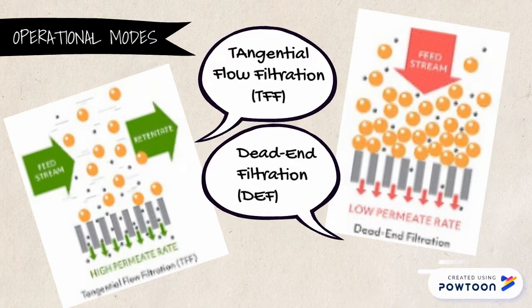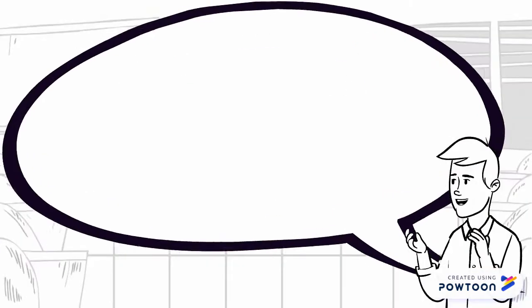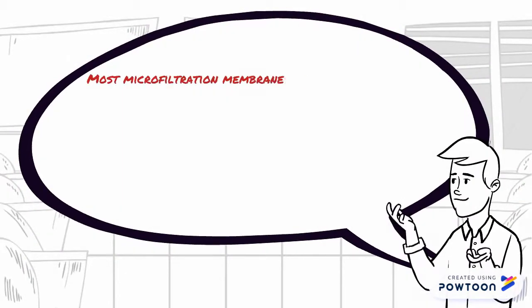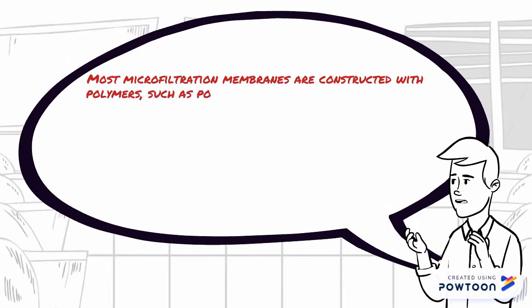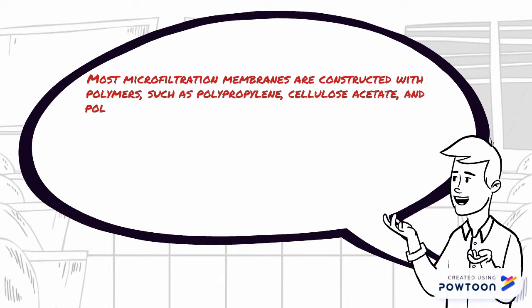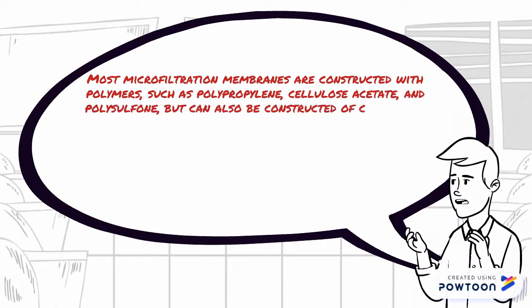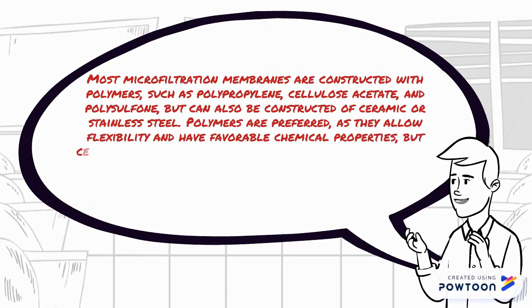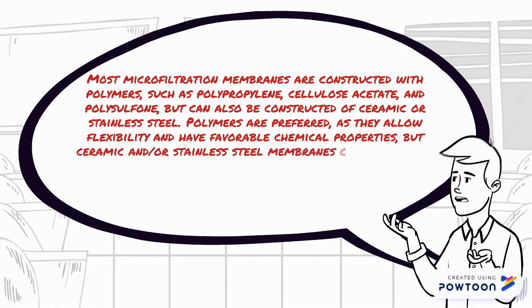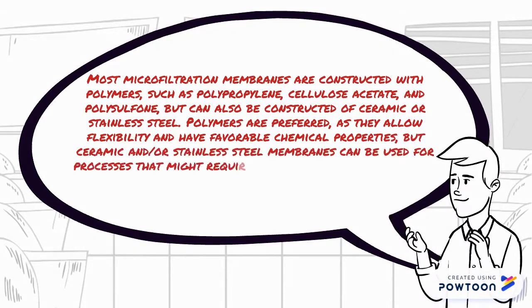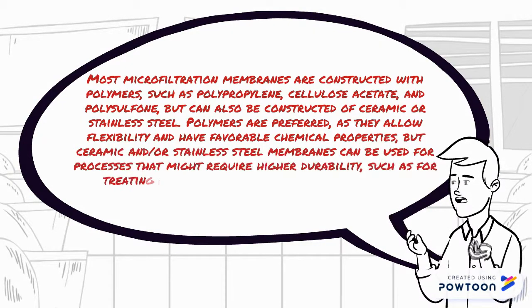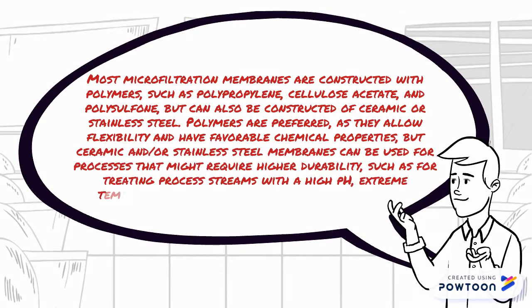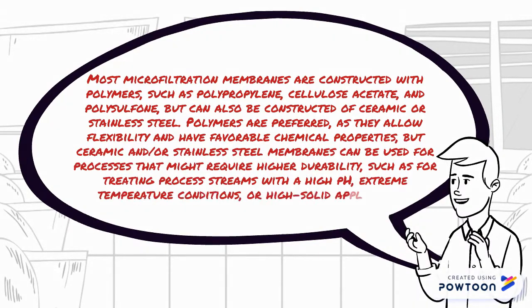Most microfiltration membranes are constructed with polymers such as polypropylene, cellulose acetate, and polysulfone, but can also be constructed of ceramic or stainless steel. Polymers are preferred as they allow flexibility and have favorable chemical properties, but ceramic and stainless steel membranes can be used for processes that require higher durability, such as treating process streams with high pH, extreme temperature conditions, or high solid applications.